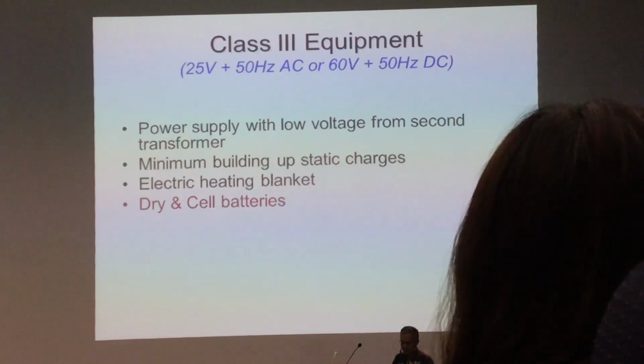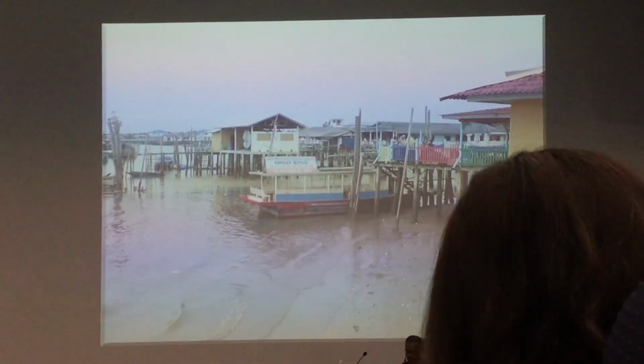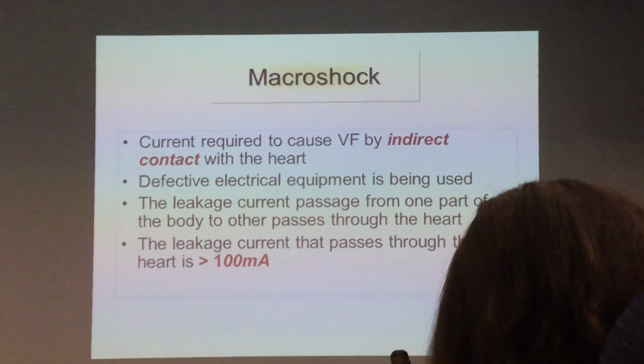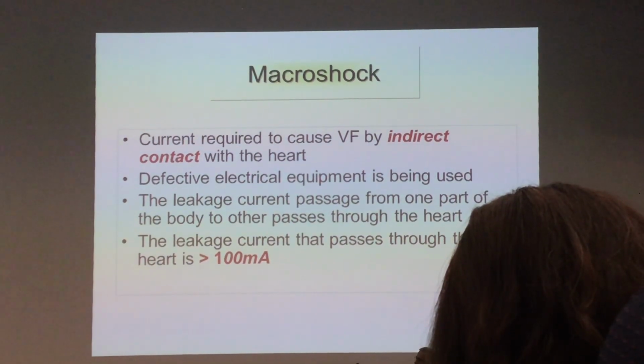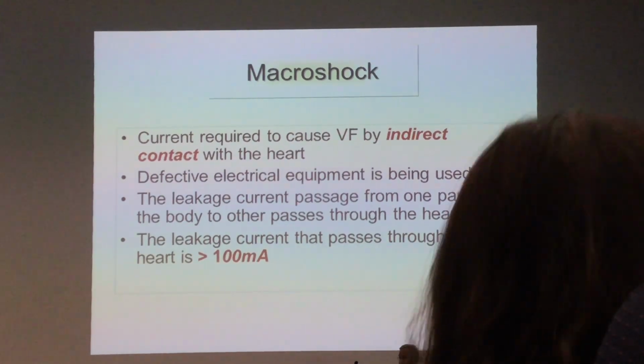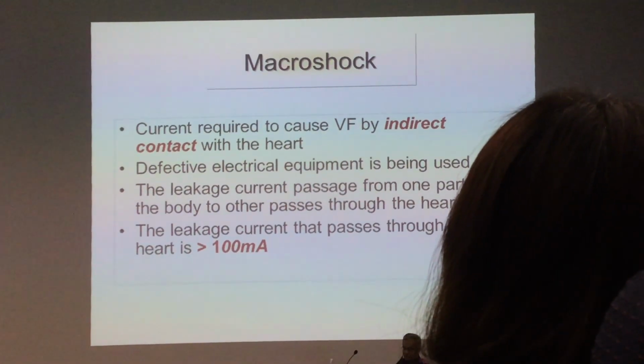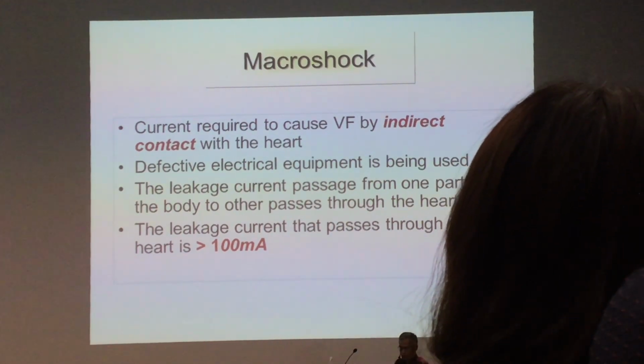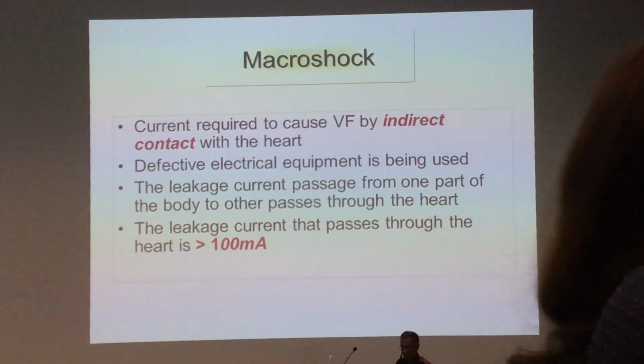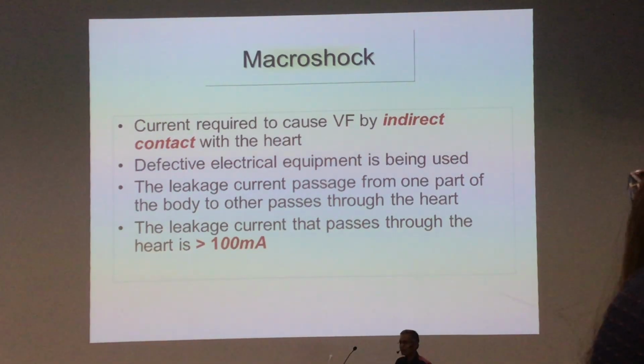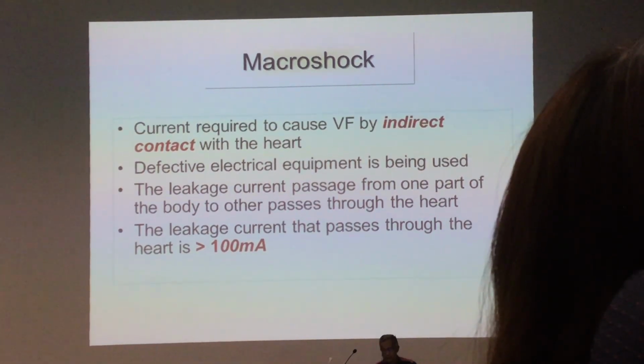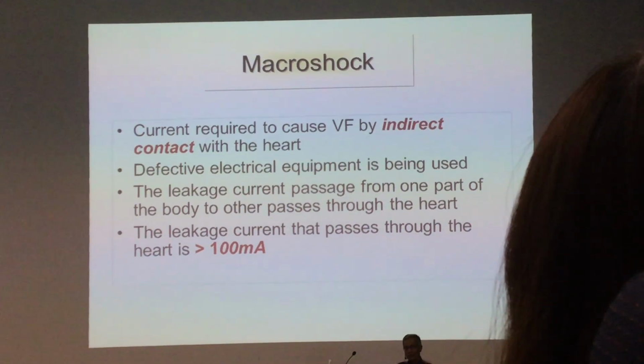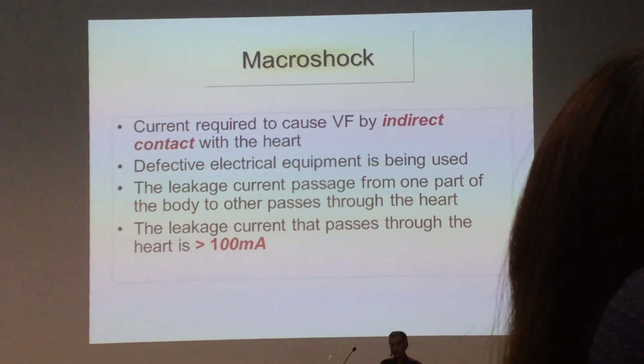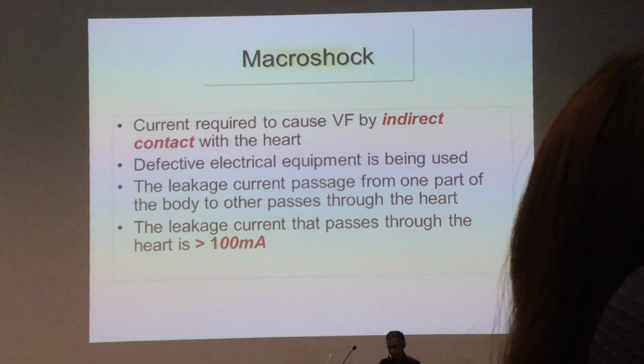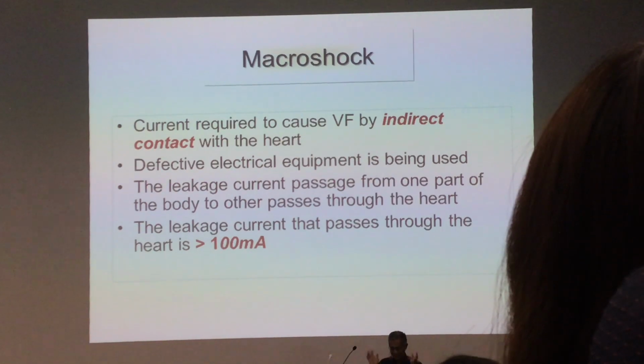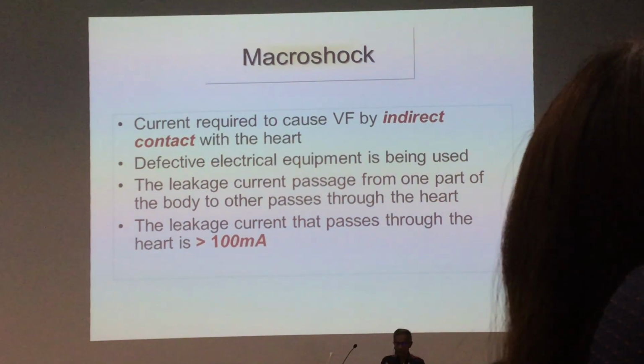This is the symbol. The battery is straightforward. Now, as I mentioned earlier, macroshock occurs when the current goes through your body via the skin. So you need a bigger current to cause VF, up to 100 milliamp, which means it's not easy to get electrocuted by touching faulty equipment, unless your hands are wet. If your hands are wet, then you may get electrocuted. Just remember, whenever you want to touch an equipment, your hands must be dry, or you wear gloves. We do not know whether this machine is faulty or not.